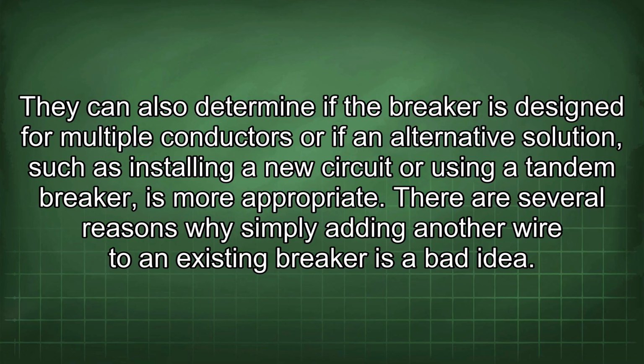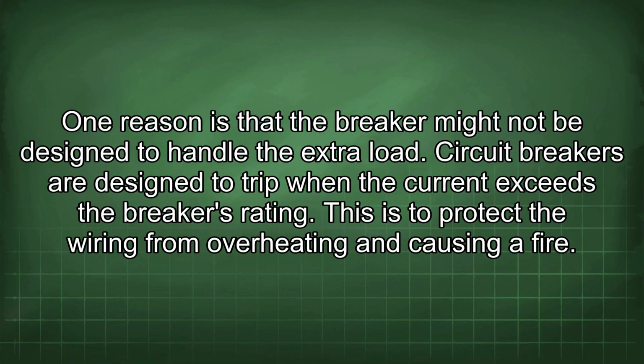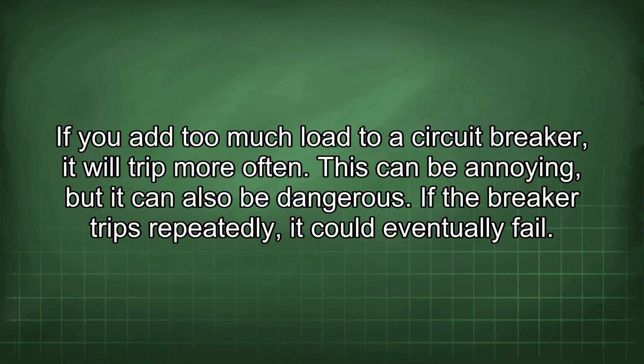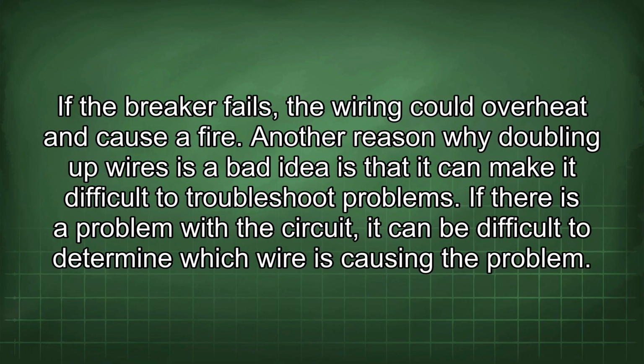There are several reasons why simply adding another wire to an existing breaker is a bad idea. One reason is that the breaker might not be designed to handle the extra load. Circuit breakers are designed to trip when the current exceeds the breaker's rating. This is to protect the wiring from overheating and causing a fire. If you add too much load to a circuit breaker, it will trip more often. This can be annoying, but it can also be dangerous. If the breaker trips repeatedly, it could eventually fail. If the breaker fails, the wiring could overheat and cause a fire.